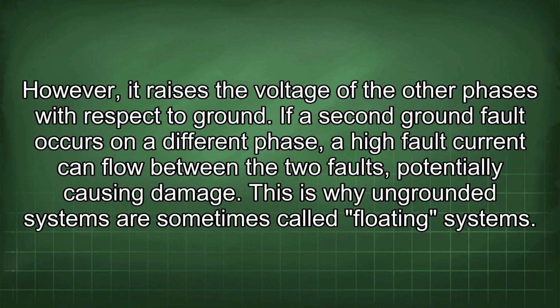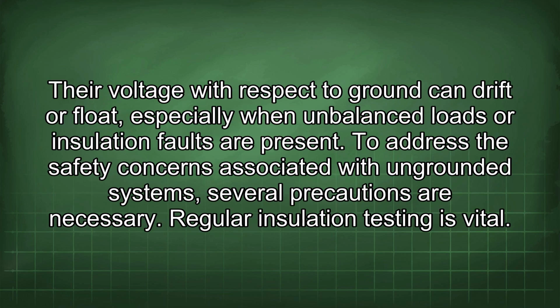However, it raises the voltage of the other phases with respect to ground. If a second ground fault occurs on a different phase, a high fault current can flow between the two faults, potentially causing damage. This is why ungrounded systems are sometimes called floating systems. Their voltage with respect to ground can drift or float, especially when unbalanced loads or insulation faults are present. To address the safety concerns associated with ungrounded systems, several precautions are necessary.